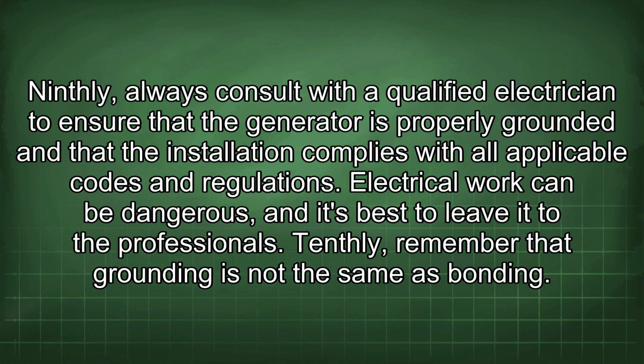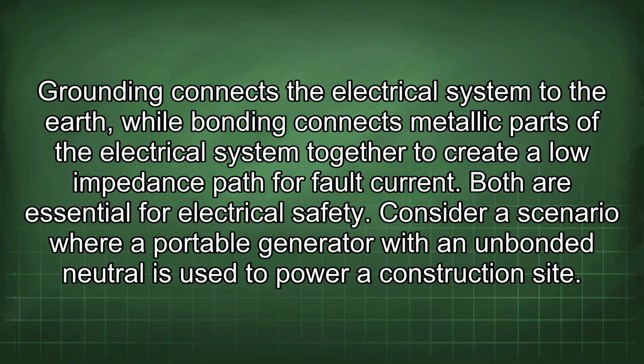Electrical work can be dangerous, and it's best to leave it to the professionals. Tenthly, remember that grounding is not the same as bonding. Grounding connects the electrical system to the earth, while bonding connects metallic parts of the electrical system together to create a low impedance path for fault current. Both are essential for electrical safety.